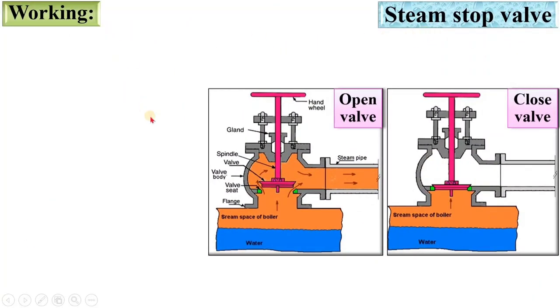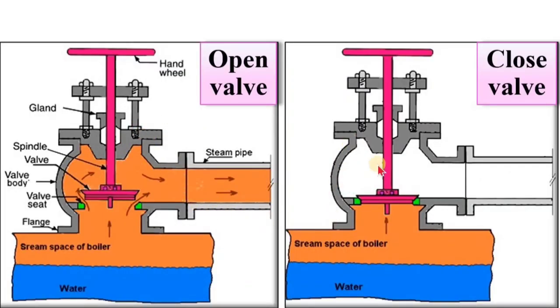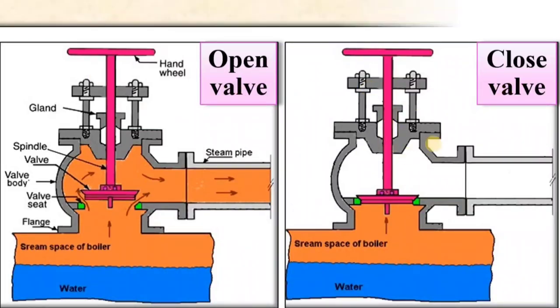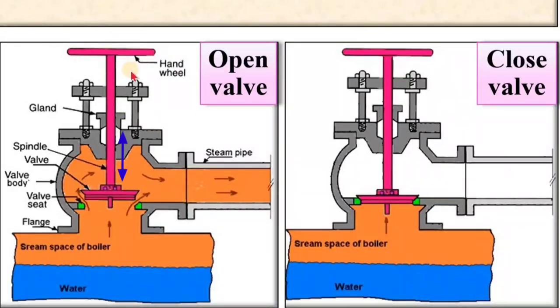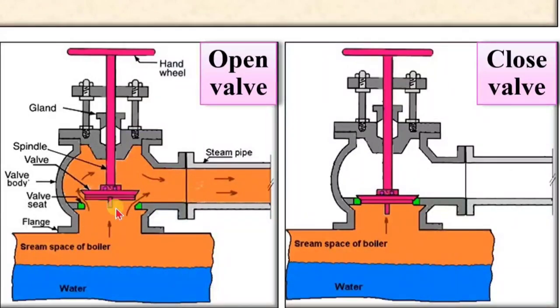Next, the working of the steam stop valve. Here you can see two different positions of the steam stop valve: one is in open condition and another is in close condition — simply on and off. By default the valve is in close condition and steam is not allowed to pass through the valve. When the spindle is rotated by the hand wheel, the valve moves up and down according to the direction of rotation. When the valve moves up, the steam in the boiler is allowed to pass through the steam stop valve from the boiler shell to the steam pipe.